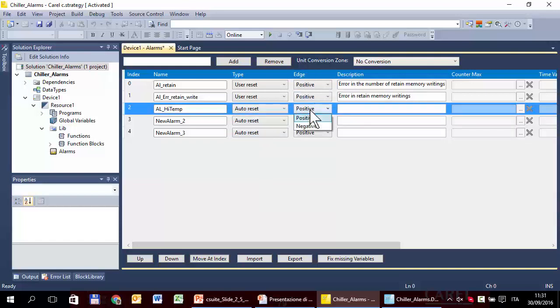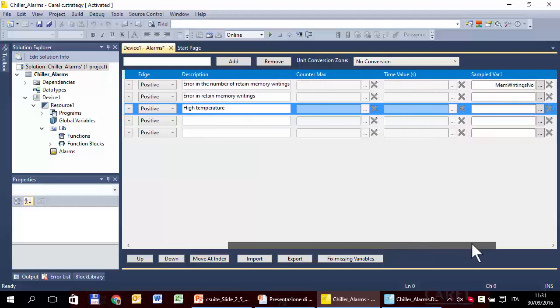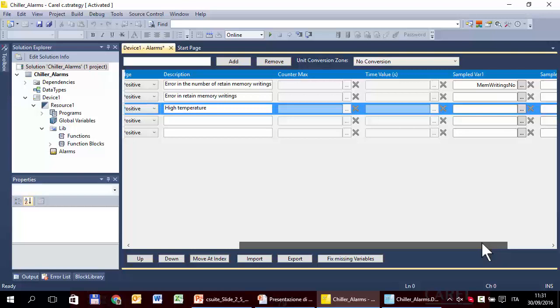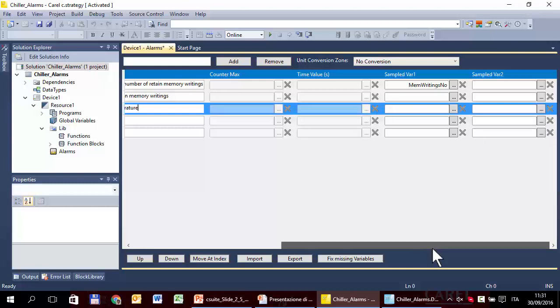Edge could be positive or negative. Positive means the alarm starts when the alarm variable changes from false to true. Negative is when it changes from true to false. Typical is positive. Then there is a description. Counter max and time value are used in the third type of alarm. Here are the two variables that you can save together with the alarm.